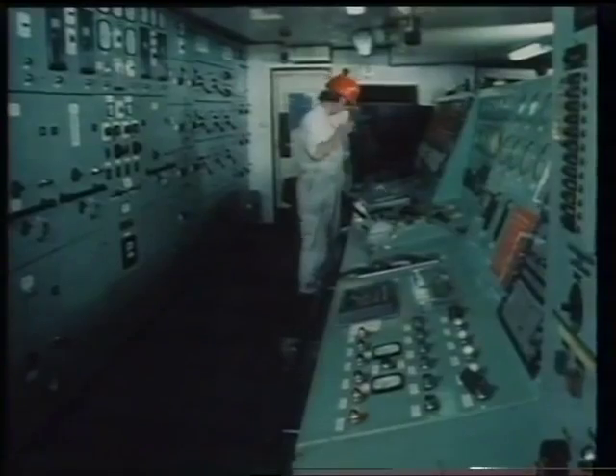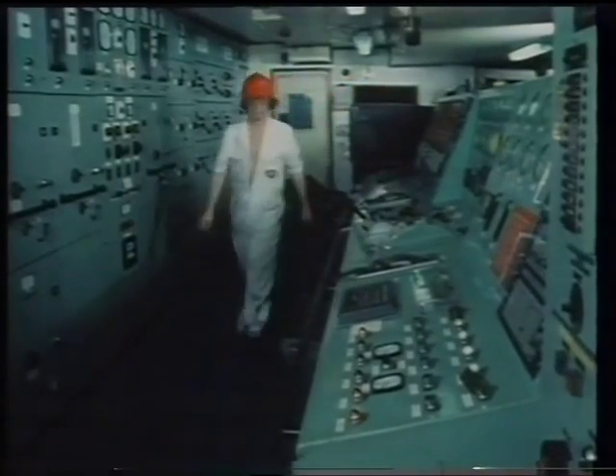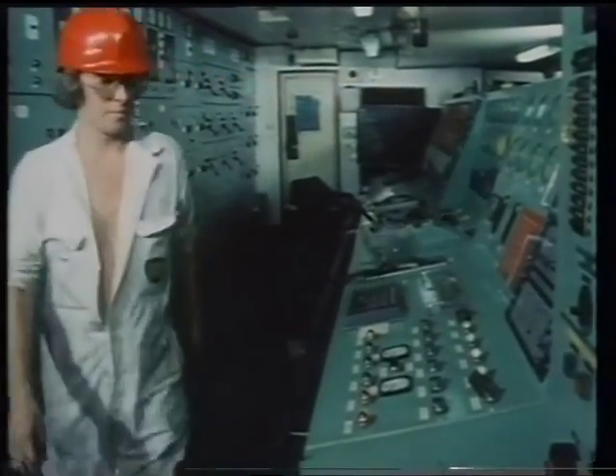What if the excitation is working well, but the AC generator still fails to generate AC output? This fault, if it occurs, usually shows up when an AC generator is started up, ready for synchronizing with other units.